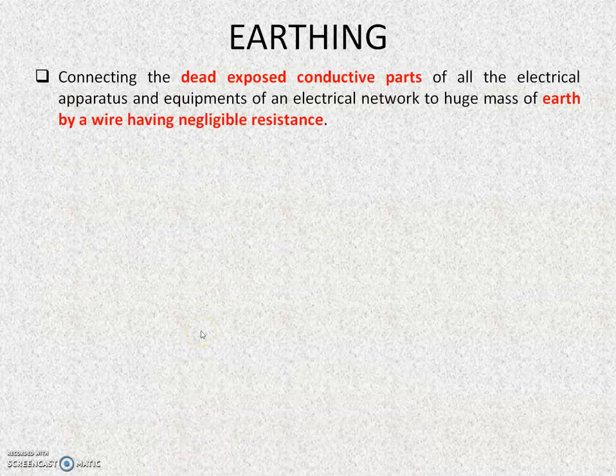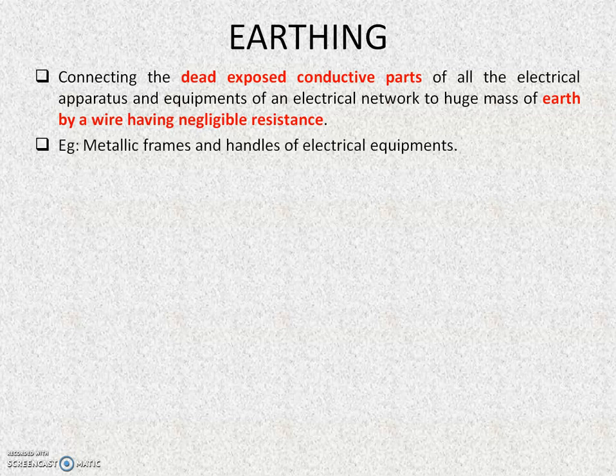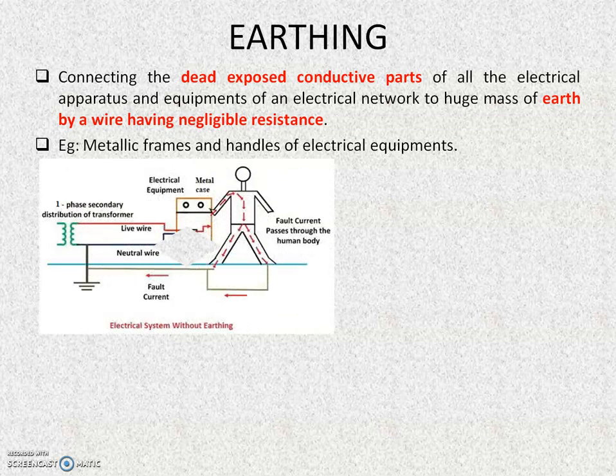Earthing. It is connecting the dead, exposed conductive parts of all electrical apparatus and equipments of an electrical network to the huge mass of earth by a wire having negligible resistance. And this is mainly done at the user end and to save the personnel or the operator. So we'll be connecting the metallic frames, handles of equipments, etc. to earth.